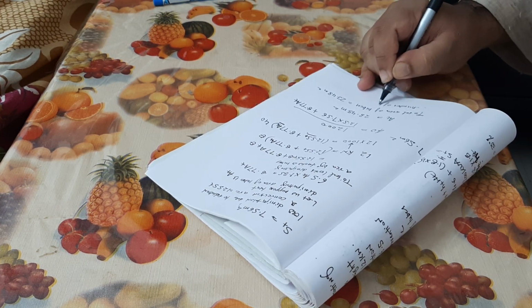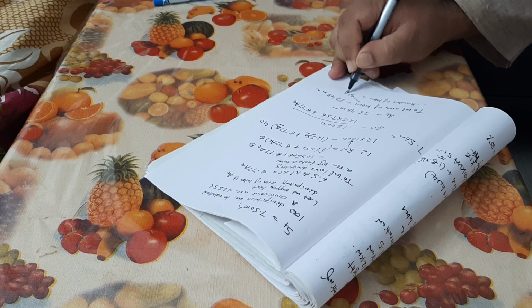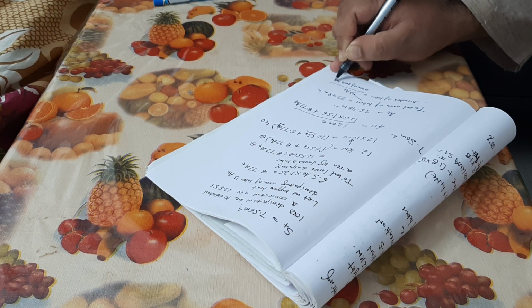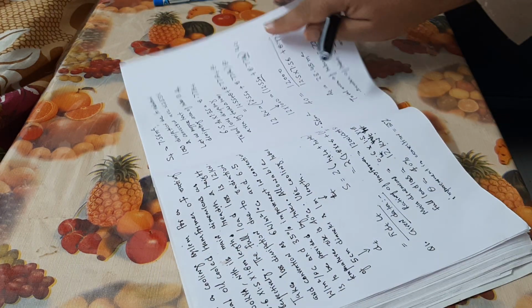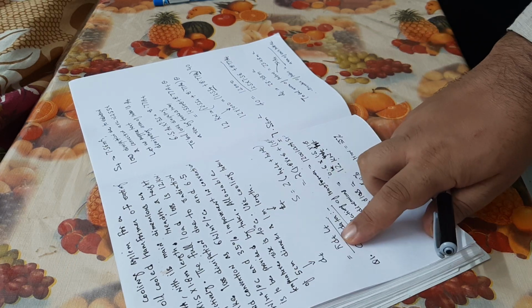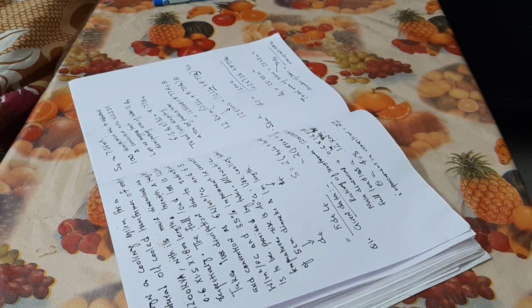Now the number of tubes would be how much? Number of tubes would be total area of tubes, that is At, divided by area of each tube, if area of each tube is represented by small a t. So area of each tube we can calculate. How do we go about the area of each tube? In the previous section only, I have shown you the area of each tube would be pi dt lt. This dt can be represented by 0.05, and lt is directly given as 1 meter. So we can calculate area of each tube.